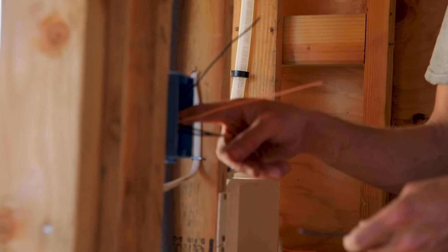Again, we're going to cut these and strip them, and strip this one also. We're going to make what's called a pigtail. Whenever we're connecting two wires together and want another one to continue, kind of like we did with the ground, we can't use the crimp ring we used with the ground wire, because these are insulated. So instead we'll use this pigtail here.